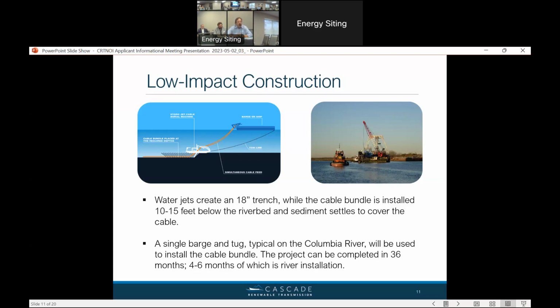The hydroplow, or jet plow, are common terms for it. They allow us to do a simultaneous cable lay burial. We have the ability to get the cable buried 10 to 15 feet into the riverbed. We'll have cable spooled on either a cable lay ship or a barge, probably more likely a barge for most of this operation. For our Neptune project, we'd have 26 miles of high voltage cable, 26 miles of neutral voltage cable, and 26 miles of fiber optic, bundled together.